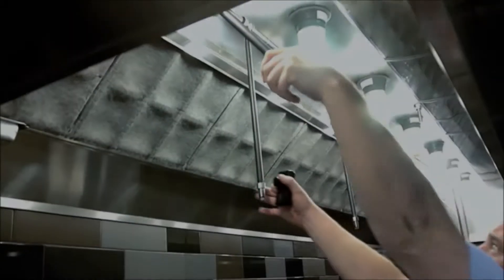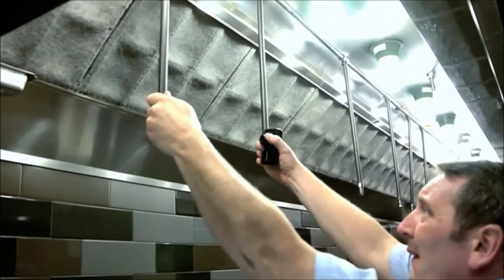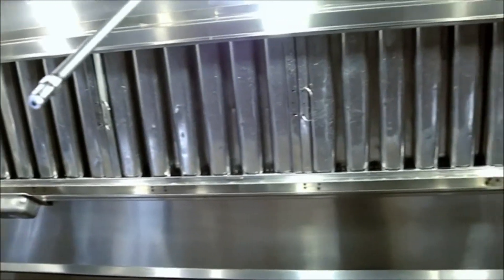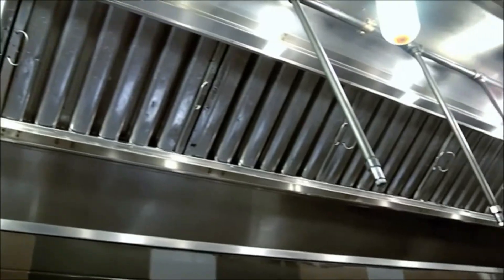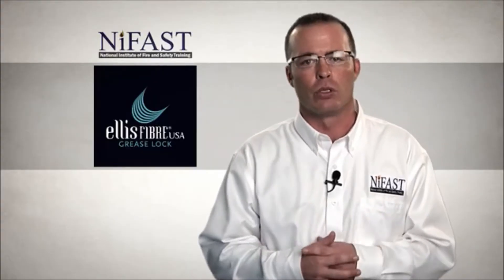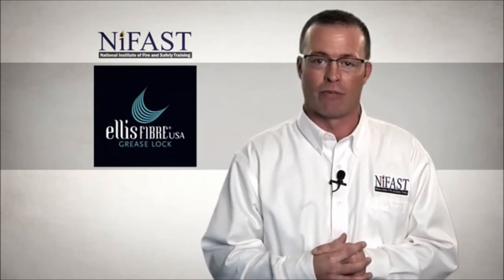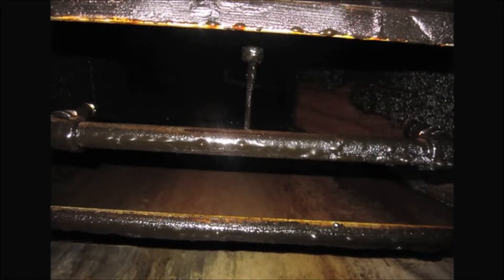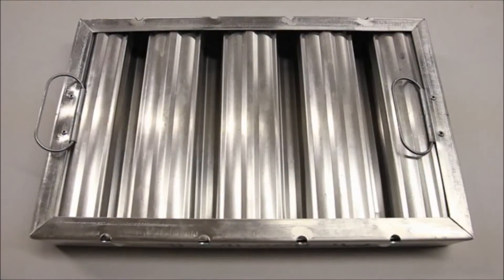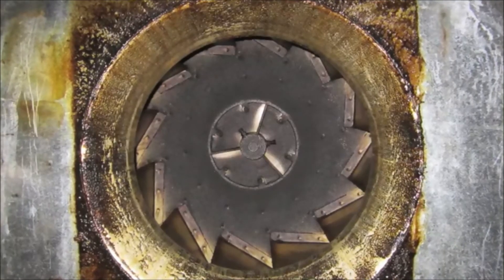The grease lock system is suitable for use in kitchen exhaust systems in conjunction with UL 1046 and ULC S649 listed metal baffle filters. The grease lock filters significantly reduce the amount of airborne grease effluent that reaches the inside of the exhaust hood system, including grease baffle filters, fan motor blades, and ducts.